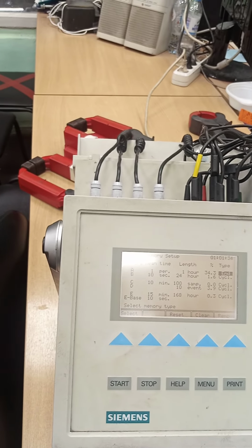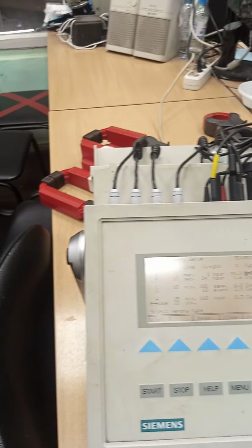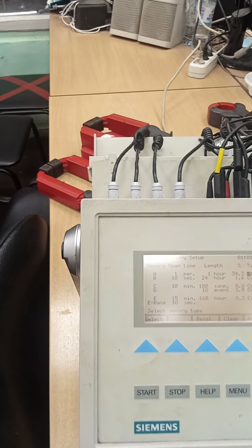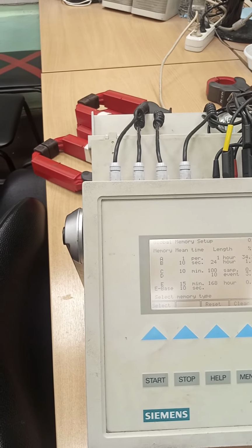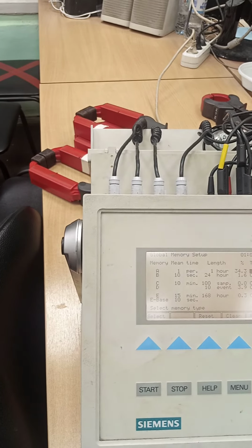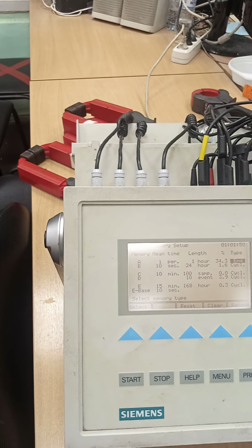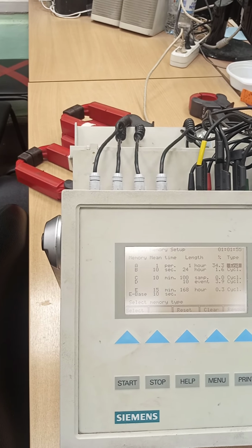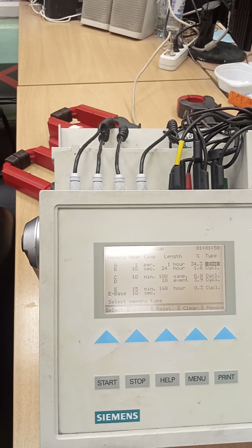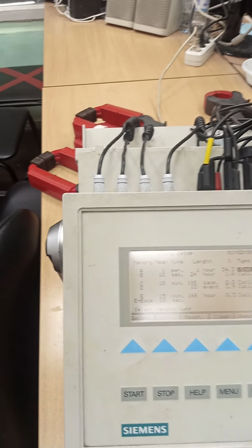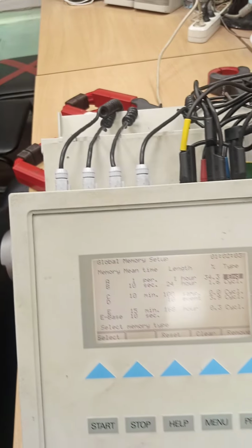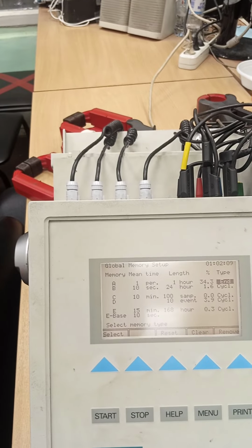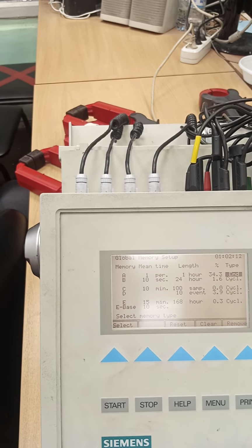So in this case, it's better to set up end buffer, end memory. So it will start measuring, and after 48 hours it will stop, and all this data will be stored, and it will wait for me until Friday, until Saturday, until next month. Okay.